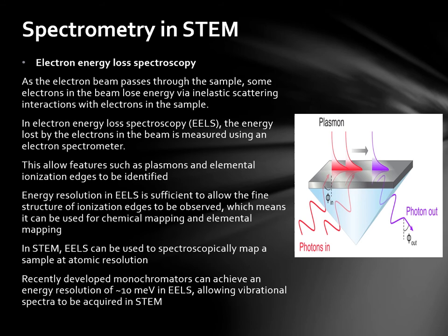There are various types of spectrometry in STEM. Firstly, we have electron energy loss spectroscopy. As the electron beam passes through the sample, some electrons in the beam lose energy via inelastic scattering interactions with electrons in the sample. In EELS, the energy lost by the electrons in the beam is measured using an electron spectrometer. This allows features such as plasmons and elemental ionisation edges to be identified. Energy resolutions in EELS are sufficient to allow the fine structure of ionisation edges to be observed, which means it can be used for chemical mapping and elemental mapping. In STEM, EELS can be used to spectroscopically map a sample at atomic resolution. Recently developed monochromators can achieve an energy resolution of 10 meV in EELS, allowing vibrational spectra to be acquired in STEM.